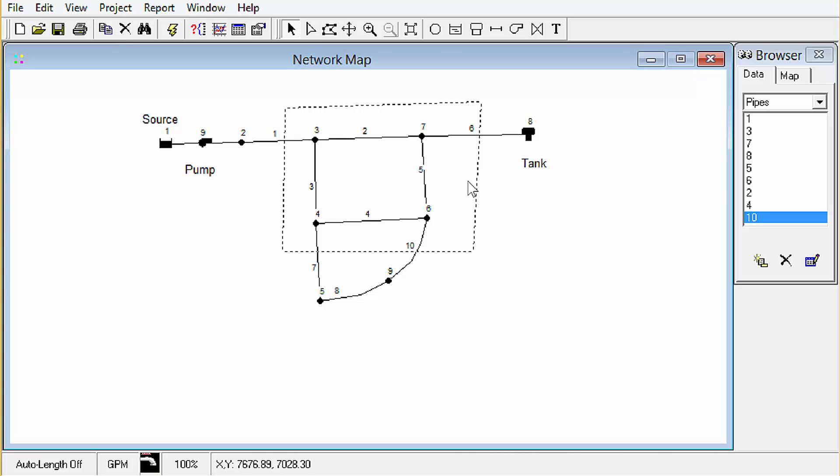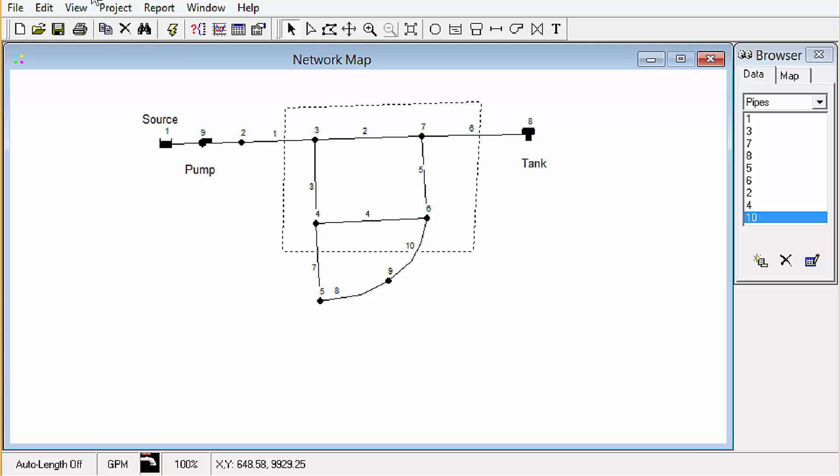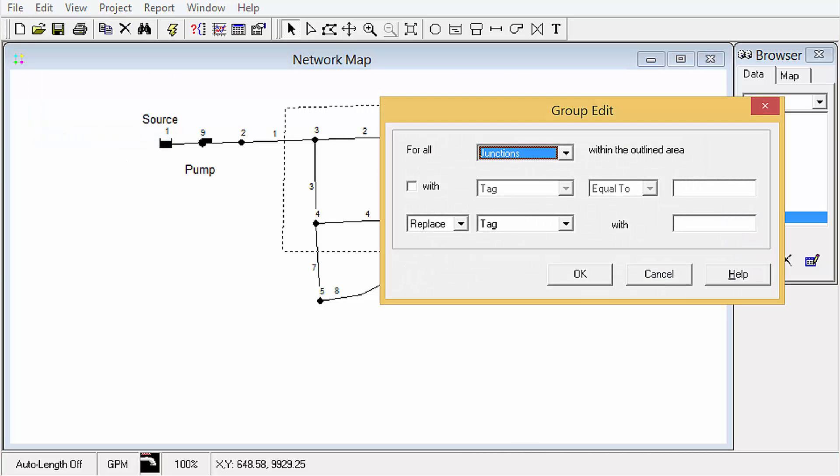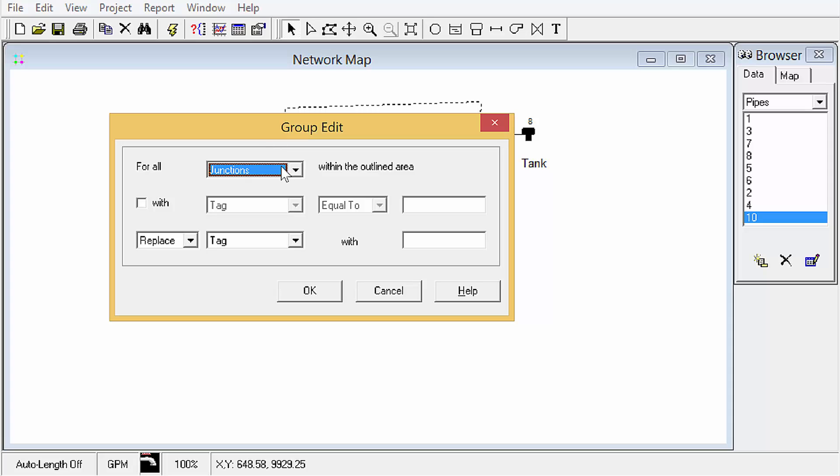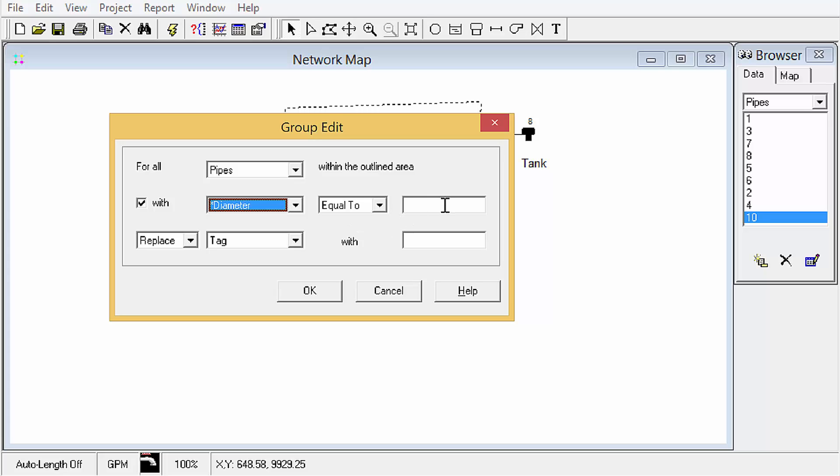Now one thing to note some commercial packages and packages like AutoCAD allow you to select whether the selection mode has to be all-inclusive or whether you can use a crossing as a window or crossing. EPAnet is a window selection method so that means the only things that will be selected are those that completely lie within this boundary. So if we're looking at editing pipes we'll only have four selected here. So if we go back to edit group edit we can select which type of element we want to edit. We can even put a query in here by using this with statement and setting. There's some simple query language in here like you could do diameter equal to 12 and it would only edit those.